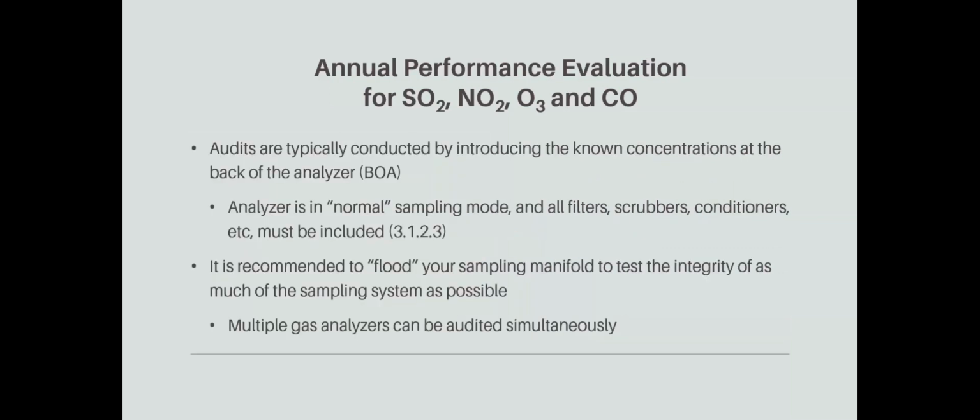So audits for APEs are typically conducted what's known as back of analyzer, or BOA. You still need to make sure that the analyzer is in your normal sampling mode and that you're sending your audit gases through all your filters, scrubbers, conditioners, etc. And that's listed in the CFR. That's 3.1.2.3 in Appendix A.